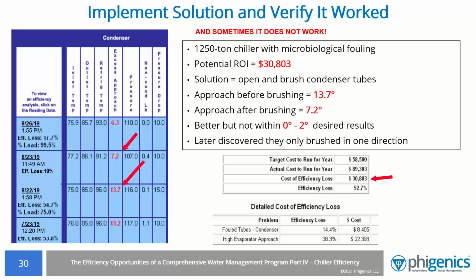So what went wrong? This type of work is often done by an outside vendor. So with proper data analysis, you can now verify if the vendor did what they said they were going to do. After further investigation, it was discovered that the vendor had only brushed the tubes in one direction, and thus the work did not achieve the targeted ROI. This is what Larry was referring to previously. You've got to do it with the right tools in the right way.